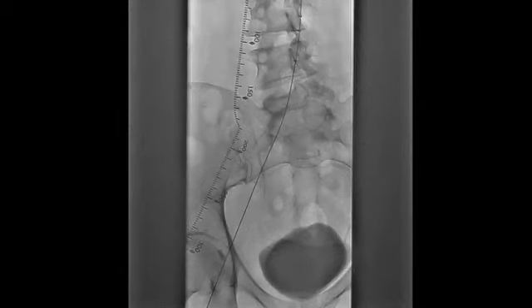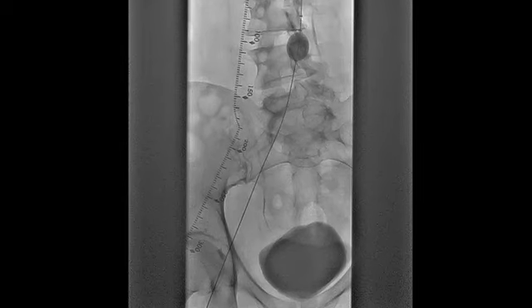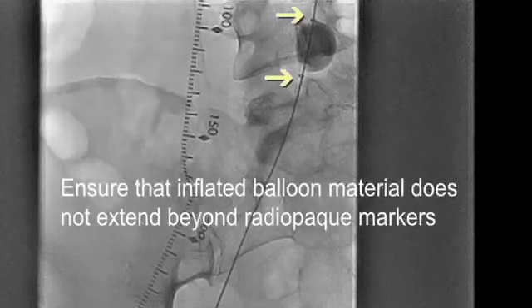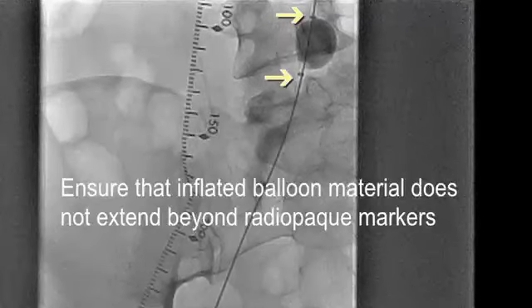For the antegrade approach, inflate Trellis system's distal balloon slowly under fluoroscopic guidance. Inflate the balloon until the sides of the balloon begin to flatten against the vessel wall. The profile of each balloon will appear spherical until it comes in contact with the vessel wall or other obstruction. To avoid overinflation, visually ensure the inflated balloon material does not extend past the radiopaque markers on either side of the balloon. Close stopcock to maintain balloon inflation.